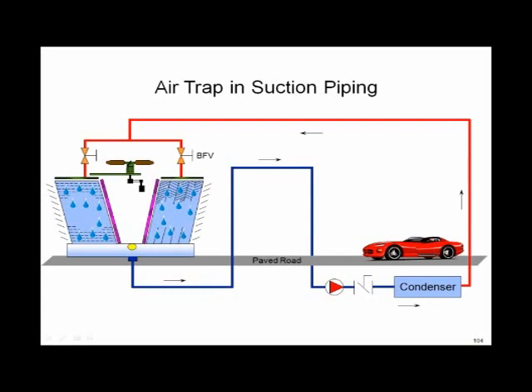And we put a garden hose in there that we could just pump water through. What we were trying to do was get the air out of that piece of pipe above the highway and get it full of water. Now, as you put water in the pipe above the pavement, obviously it's going to try to drain out through the cooling tower. Therefore, we had a guy standing in there with a piece of plywood trying to hold the water back in the tower.